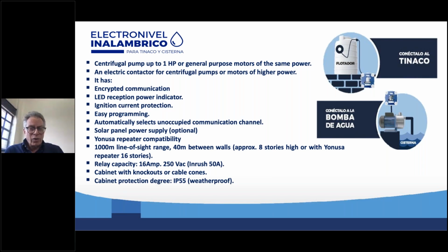The good thing is that you can turn on a pump up to 1 horsepower. The inrush current is about 40 to 42 amps for around 2 seconds, and then it settles to about 7 to 8 amps, which the contact or relay can manage perfectly.